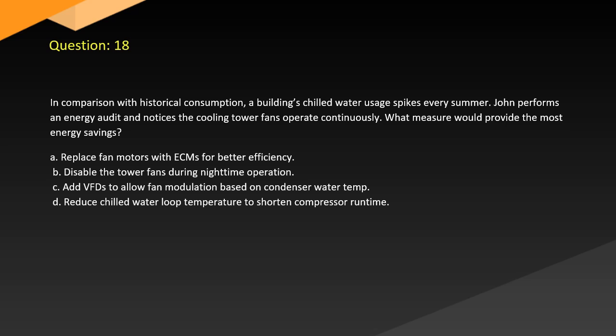Question 18. In comparison with historical consumption, a building's chilled water usage spikes every summer. John performs an energy audit and notices the cooling tower fans operate continuously. What measure would provide the most energy savings? A. Replace fan motors with ECMs for better efficiency. B. Disable the tower fans during nighttime operation. C. Add VFDs to allow fan modulation based on condenser water temp. D. Reduce chilled water loop temperature to shorten compressor runtime.